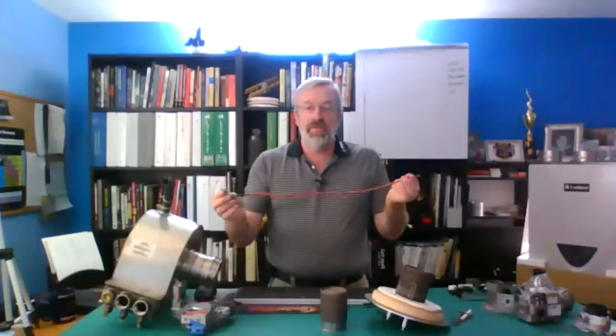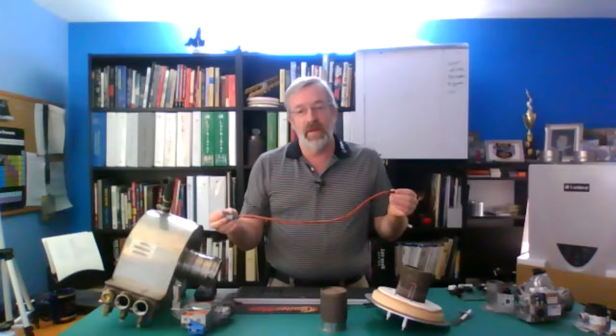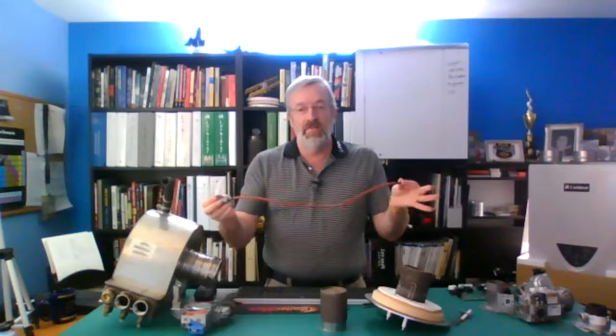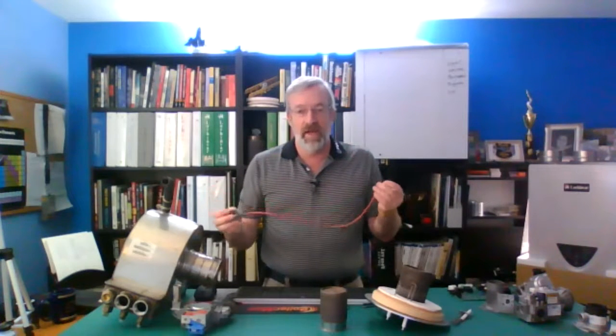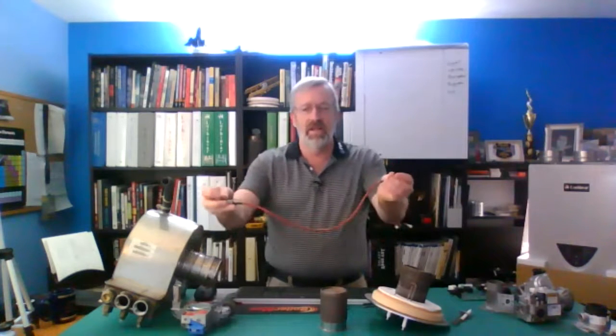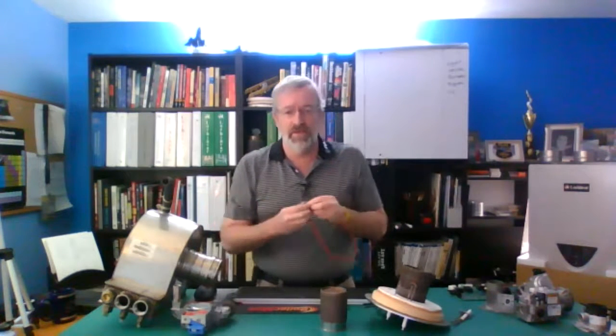Now, one of the things that we check if we're not coming out of the igniter, we're not coming out of the cable, there's a resistor in here. We want 1,000 ohms in that resistor. So go ahead and do that with your multimeter. You set it to that goofy looking horseshoe thing, set it on here. We're looking for that 1,000 ohms.